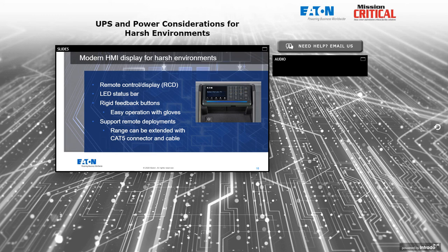An LED status bar is becoming more common on all UPSs today, where the user can, at a glance across the room, see immediately by color coding if the UPS is functioning properly. Typically, if it's green or blue, in this case, that means everything is good. If it's yellow, it means there's an alarm condition. And if it's red, it means it trips off. Most of our clients today don't have time to stop and play with their UPS every day. So they need to be able to see at a glance if everything is okay or not, and then go on to their next task.